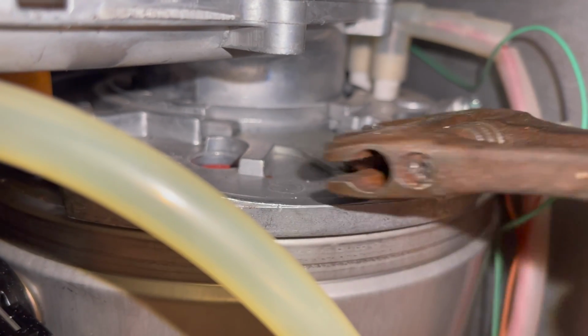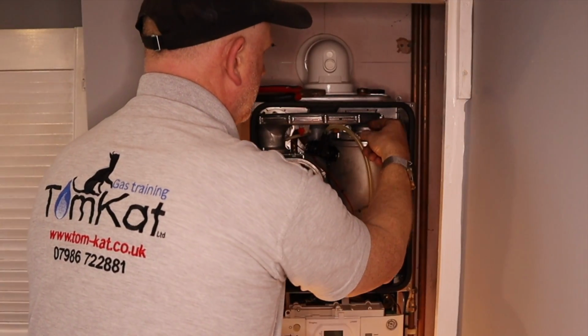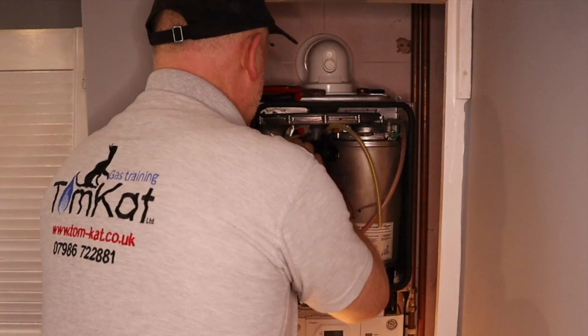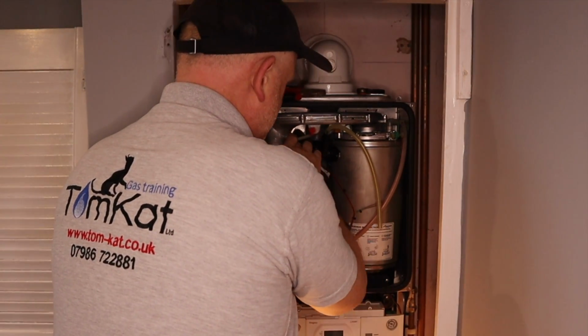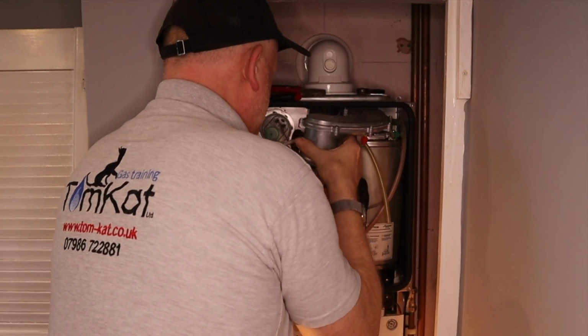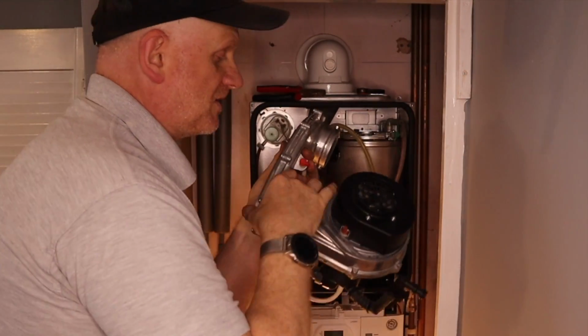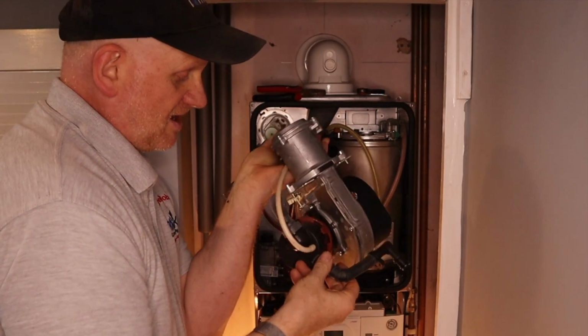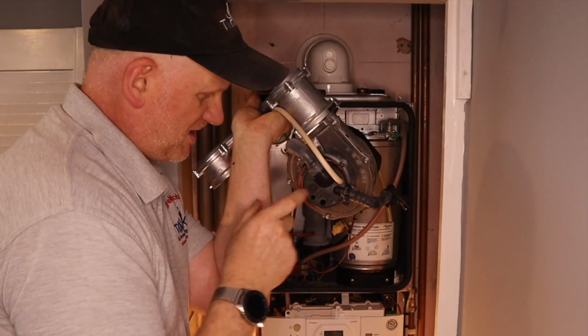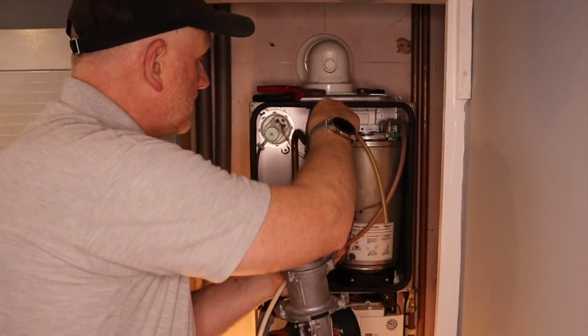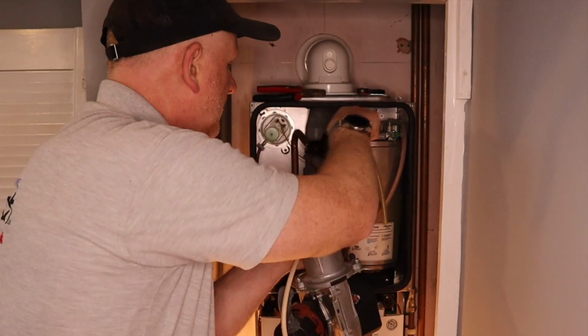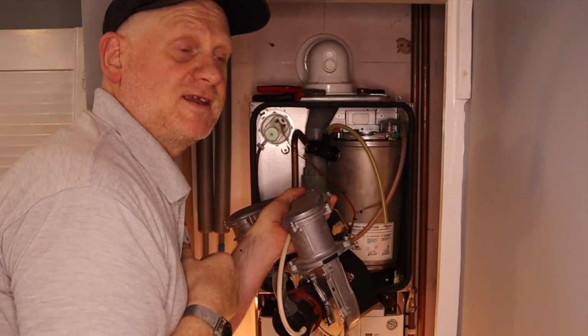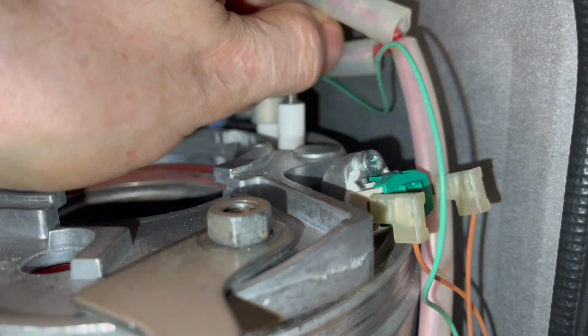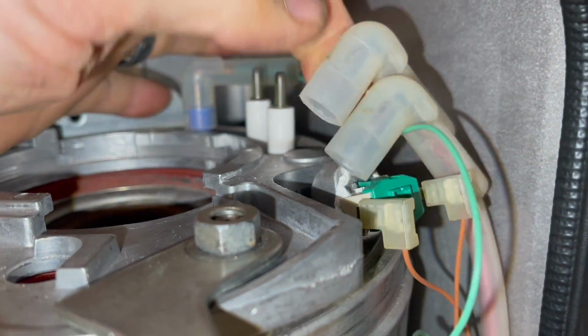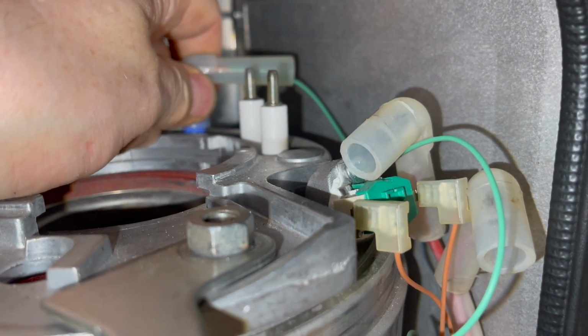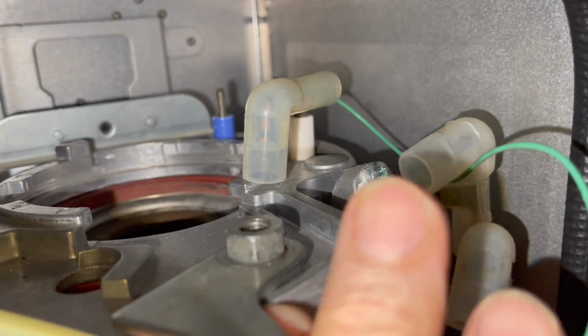Now we've undone that nut. I can just move it to the front like that, and now this burner should twist towards me and lift out, which it does. So that's how easy it is to take the fan, and we're going to look inside here to look at this bearing in a minute, but that's how you get it out easy. So now it just leaves us to get the electrodes off the top plate, and then we can start taking off inside. So we just need to get these ignition leads off, which that's the first one to come off, and then the second one, and then the flame rectification. Well, they came off easy. They're normally a lot harder than that.